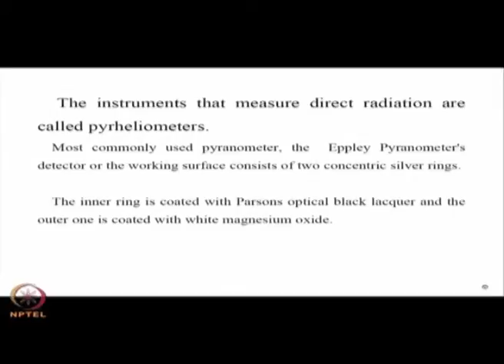The most commonly used pyranometer is the Eppley type of pyranometer, and the detector or working surface consists of two silver rings. We will come to the details along with the pictures. The inner ring is coated with Parsons optical black lacquer and the outer one is coated with white magnesium oxide. This produces a temperature difference between the black coated ring being at a higher temperature and the brightly polished material being at a lower temperature, and the temperature difference is measured by a thermopile, which is connected to a measuring device like a microvoltmeter or a millivoltmeter.